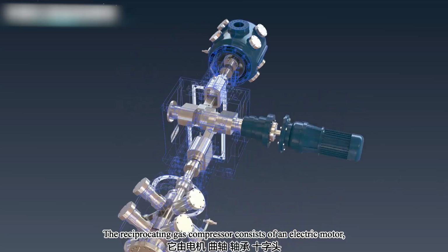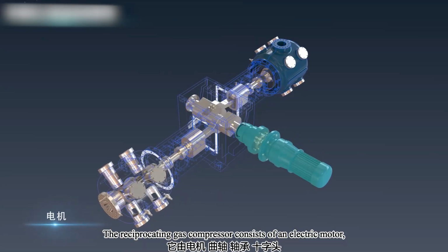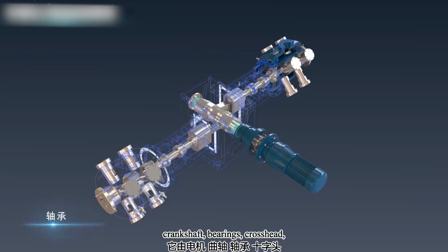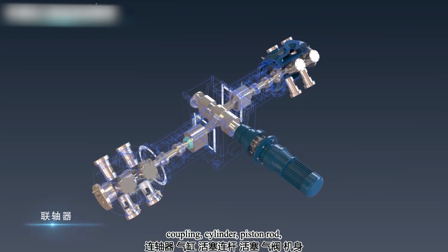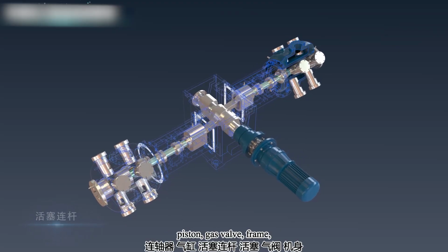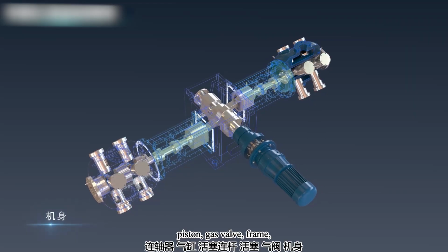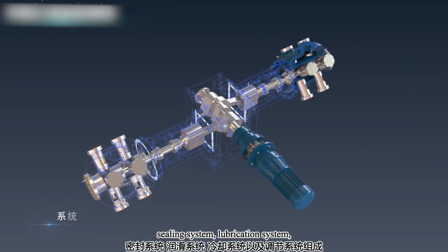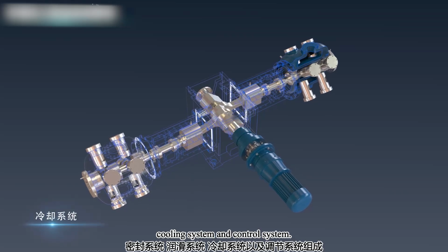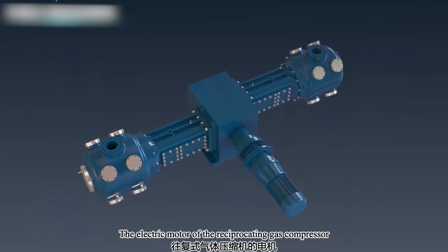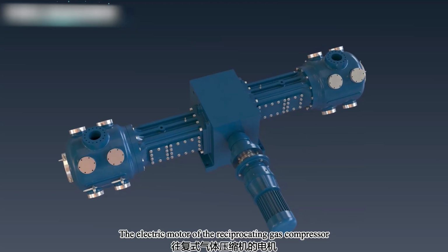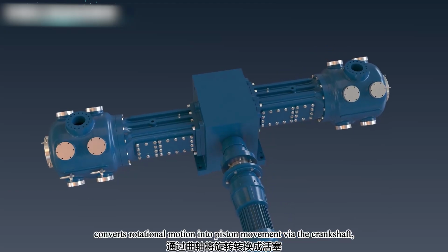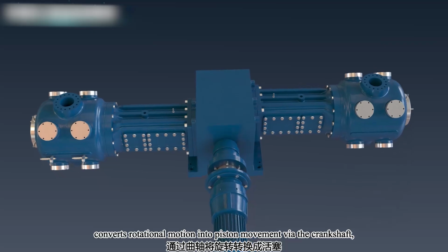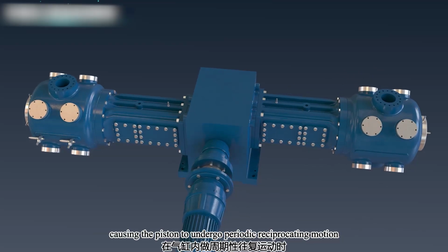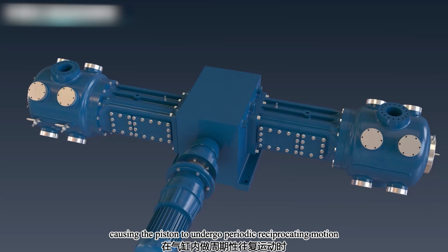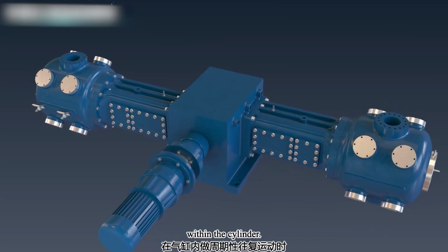The reciprocating gas compressor consists of an electric motor, crankshaft, bearings, crosshead, coupling, cylinder, piston rod, piston, gas valve, frame, sealing system, lubrication system, cooling system, and control system. The electric motor of the reciprocating gas compressor converts rotational motion into piston movement via the crankshaft, causing the piston to undergo periodic reciprocating motion within the cylinder.